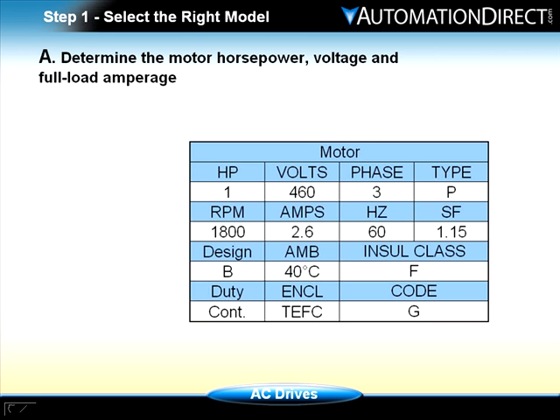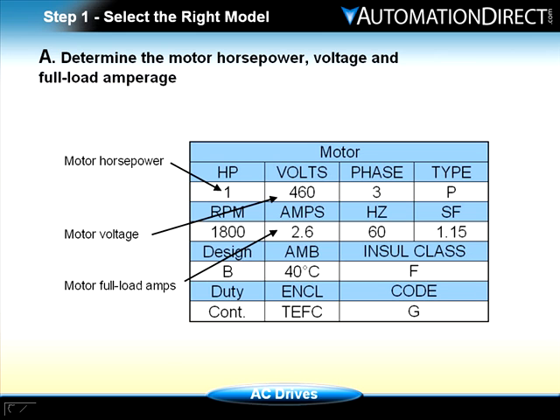In order to select the right model of AC drive for your application, you must determine the motor horsepower, voltage, and full load amperage. This information can be found on the motor nameplate. For this scenario, we are using a one horsepower, 460 volt AC motor with a full load rating of 2.6 amps, controlling a blower fan.